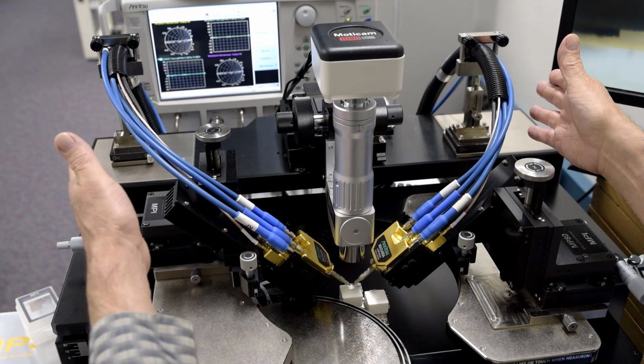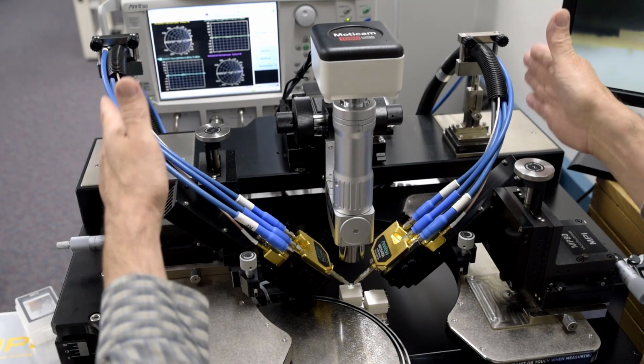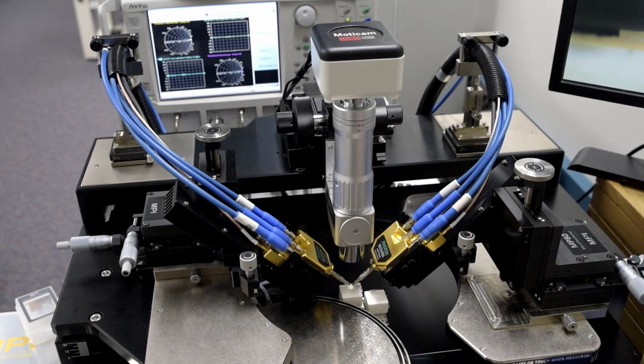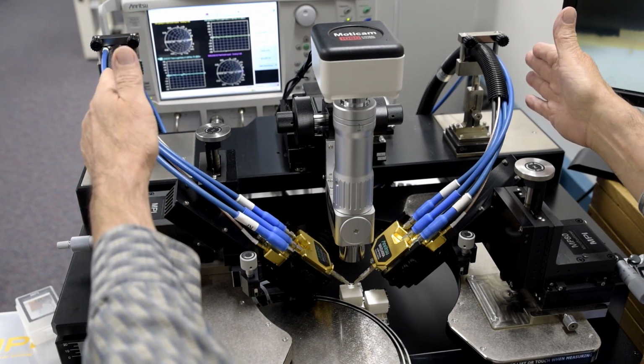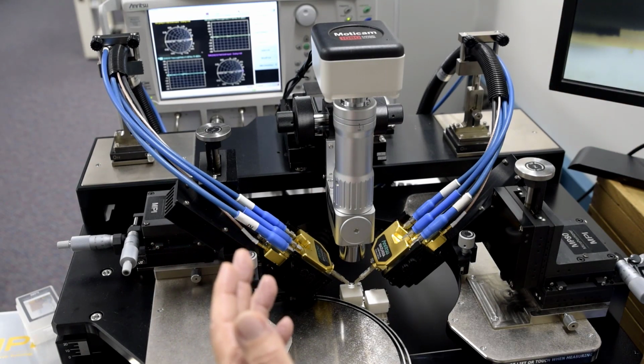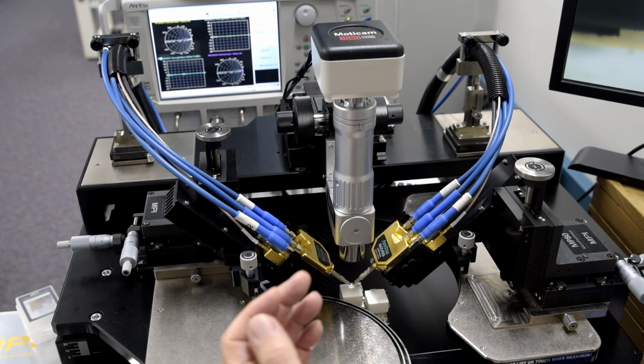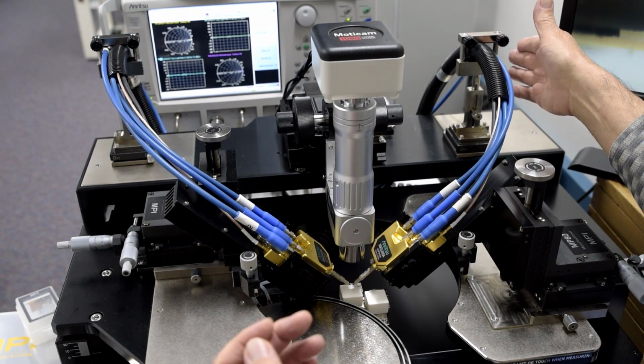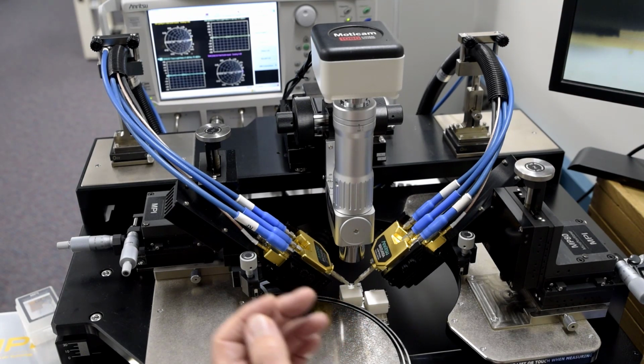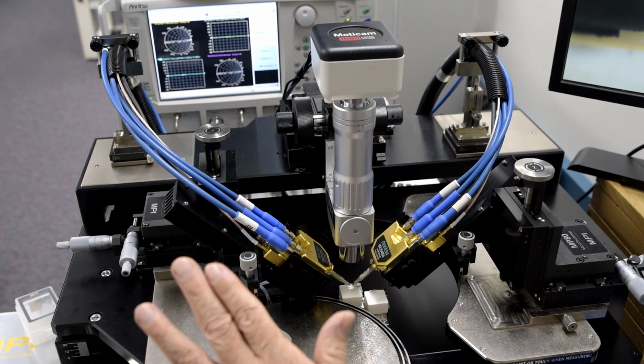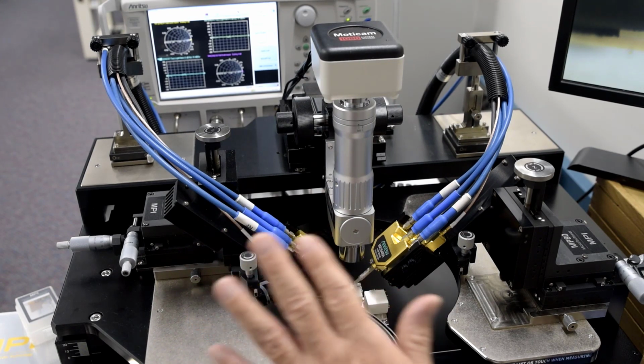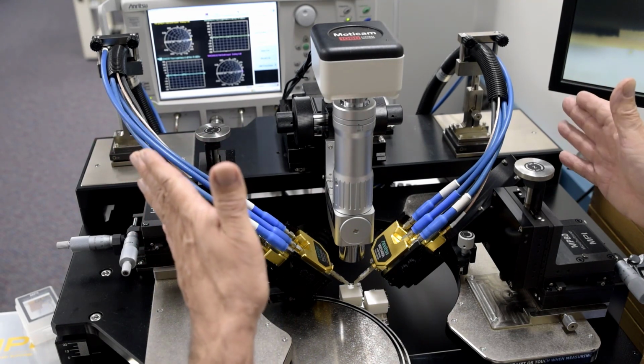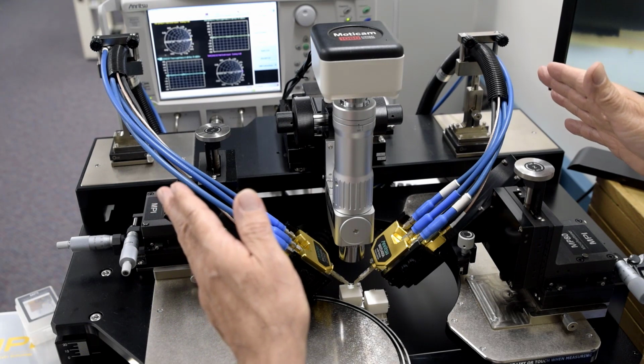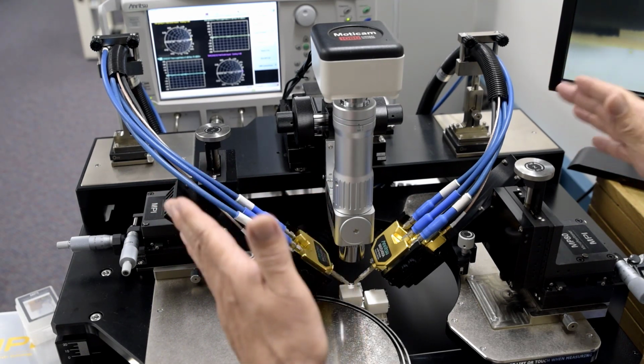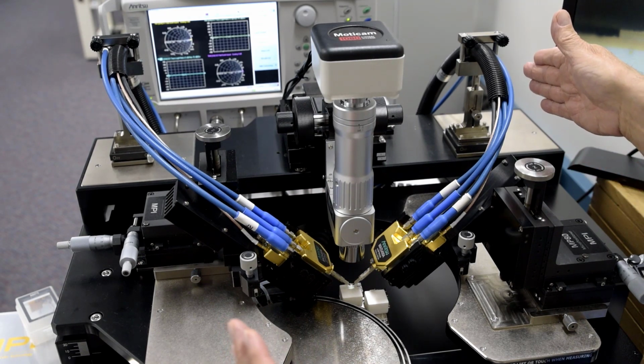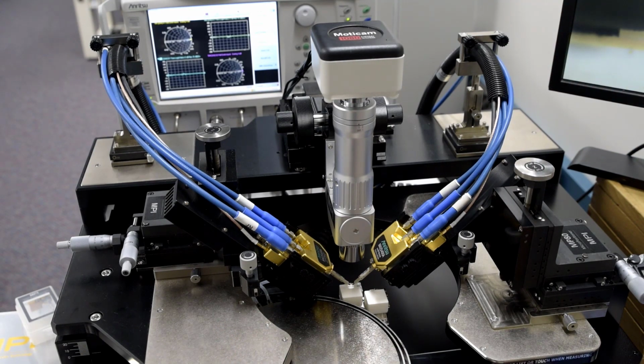So the stability of the system then is going to be dependent on the cables as they interface from the test set to the module. And so you want to provide support for the cables so that there isn't going to be a lot of flexing after calibration. And that's what we've done here. We have mounted these cable support brackets in order to hold firmly the cables in place and minimize any kind of flexing of the cables after calibration. So with this configuration, without any kind of flexing, the one key aspect of stability is going to then be determined by temperature. The thermal conductivity to the cables will be of importance.